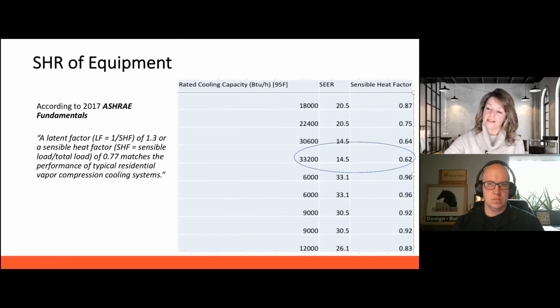What that means is 62% of the BTUs of this system are going to focus on sensible, and 38% are going to focus on latent, so the water removal. So that is a really good piece of equipment for achieving the temperature and also trying to maximize the most water removal possible. So when the system's running and it gets a good, long run time, then it's going to do a really good job of dehumidifying.